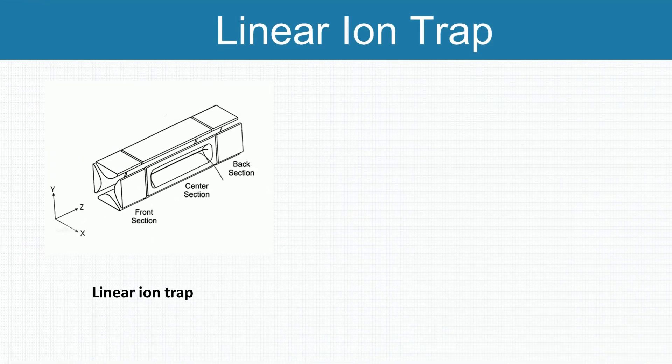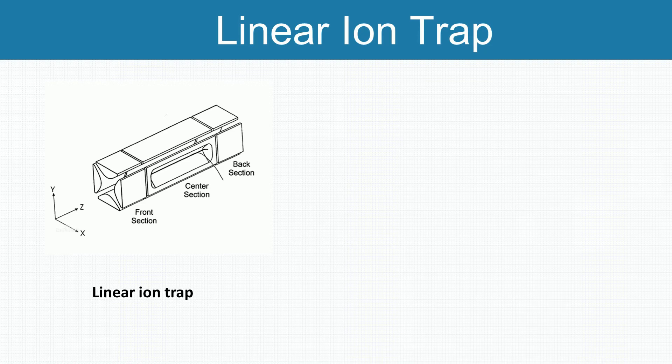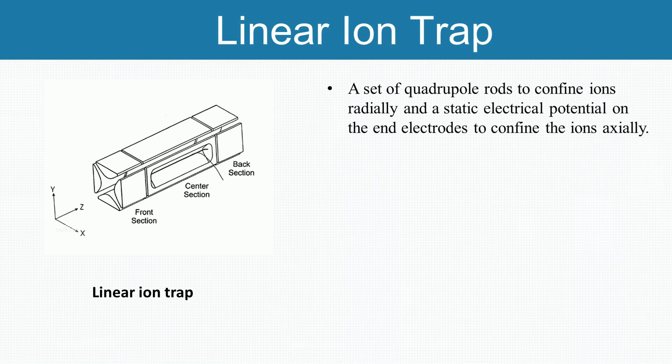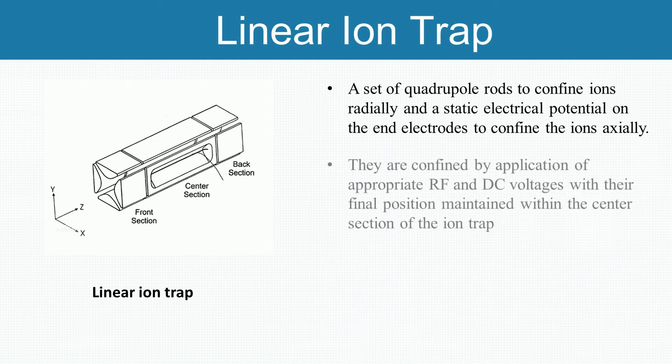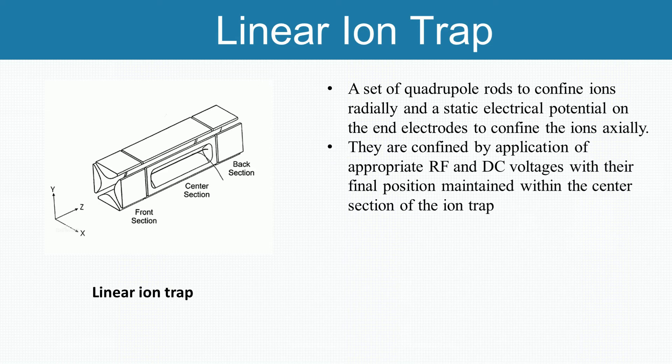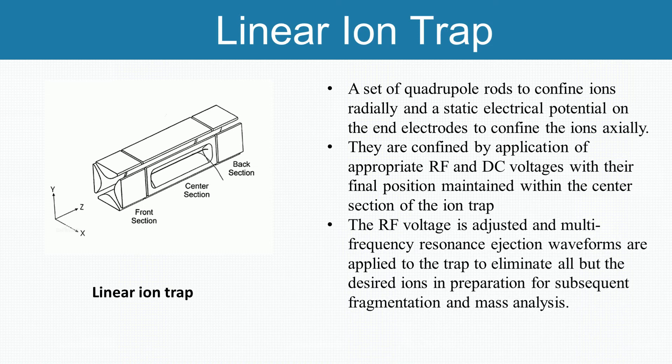By creating a potential well for the ions, the linear ion trap can be used as a mass filter or as a trap. The linear ion trap uses a set of quadrupole rods to confine ions radially by a two-dimensional radio frequency field, and a static electrical potential on end-electrodes confines the ions axially. Ions are confined by application of appropriate radio frequency and direct current voltages, with their final position maintained within the center section of the ion trap. The radio frequency voltage is adjusted, and multi-frequency resonance ejection waveforms are applied to the trap to eliminate all but the desired ions in preparation for subsequent fragmentation and mass analysis.